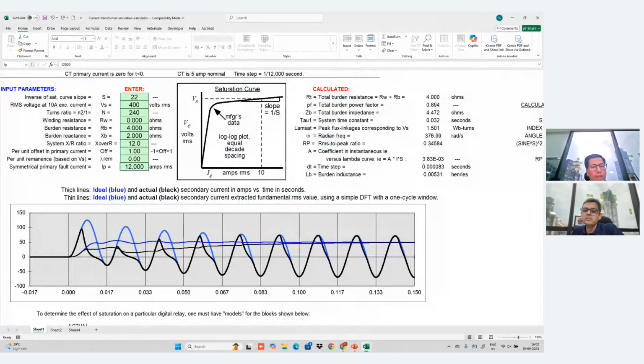Okay, so this is the Excel prepared by the IEEE members. Here, the blue color part is your actual primary current and the black color part is your saturated CT output. The blue color here is the RMS value and this is the instantaneous value. For the black color, you can see the actual RMS is on a higher side, but the CT is giving a lower output than the actual fault. This is all because of the CT saturation.